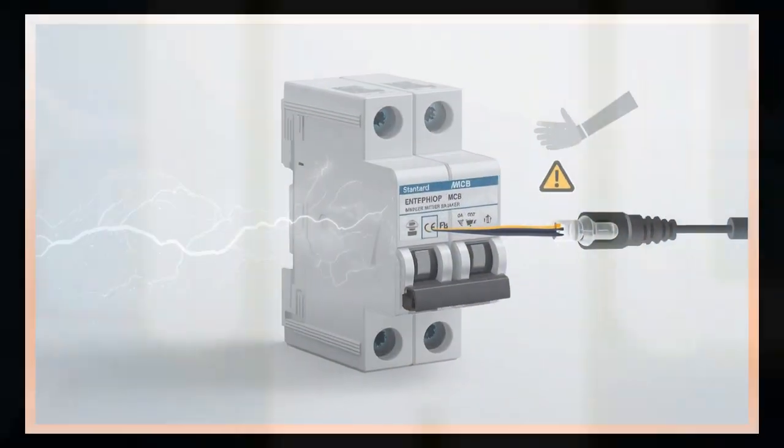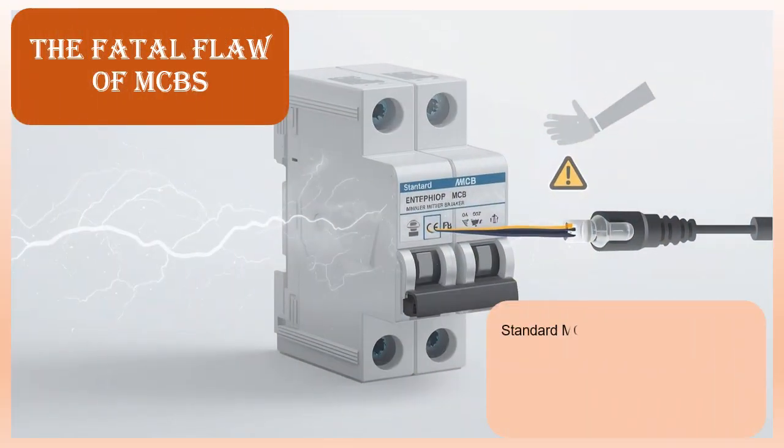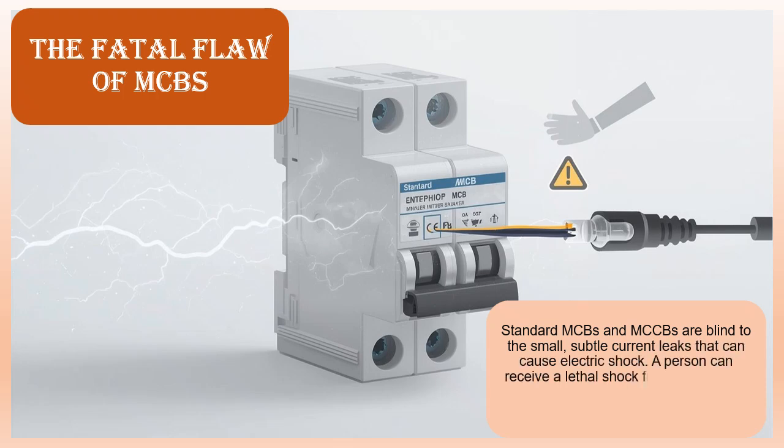The fatal flaw of MCBs. Standard MCBs and MCCBs are blind to the small, subtle current leaks that can cause electric shock. A person can receive a lethal shock from a current as low as 50 to 100 milliamps, which is far too low to trip a 15 amp MCB.